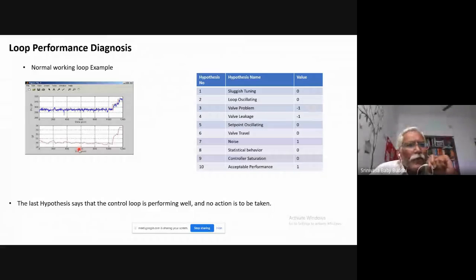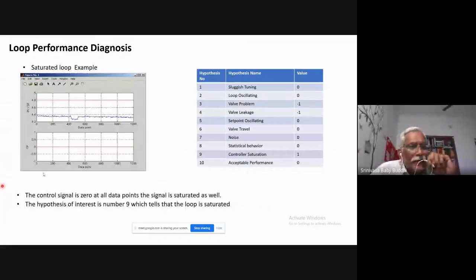Next is the saturation example. You can see here the set point is constant and the process value is varying, but the output is constant at zero value. Okay. Now, when we look at the hypothesis values, you can see that only control saturation is true, whereas all other hypothesis results are negative. So we conclude that it has a control output saturation problem. So this is how we do the identification of the performance issues in the control loop.